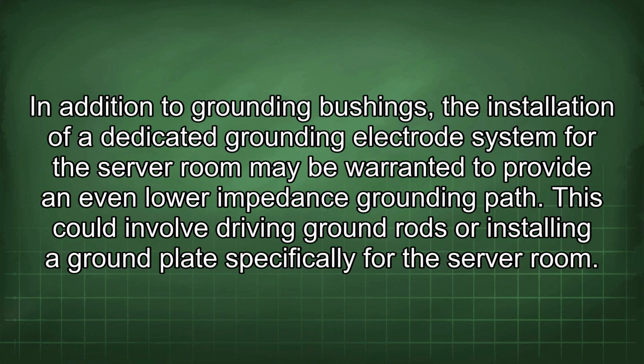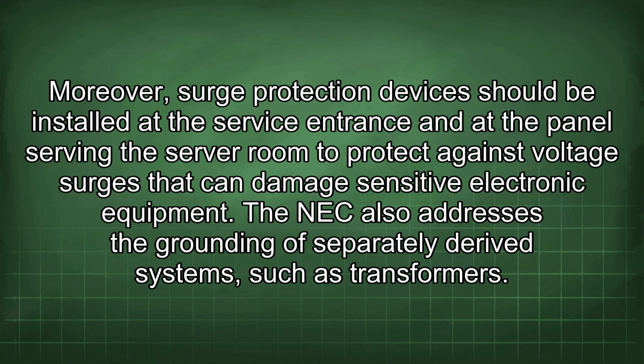In addition to grounding bushings, the installation of a dedicated grounding electrode system for the server room may be warranted to provide an even lower impedance grounding path. This could involve driving ground rods or installing a ground plate specifically for the server room. Moreover, surge protection devices should be installed at the service entrance and at the panel serving the server room to protect against voltage surges that can damage sensitive electronic equipment. The NEC also addresses the grounding of separately derived systems such as transformers.